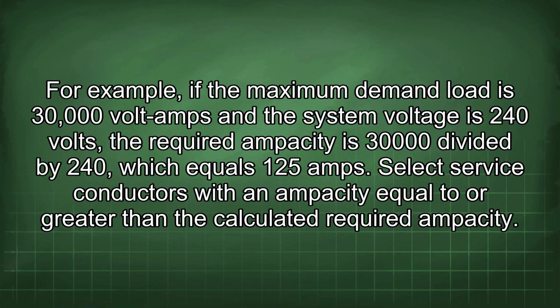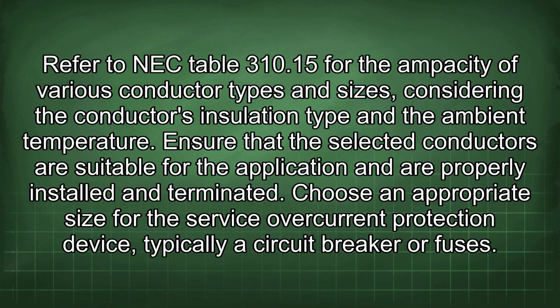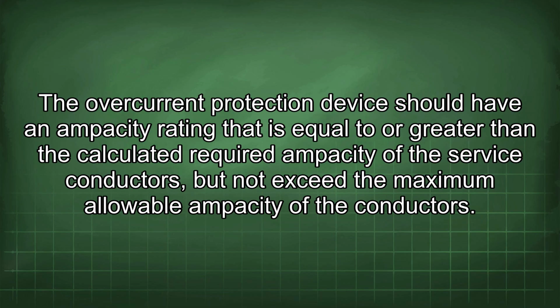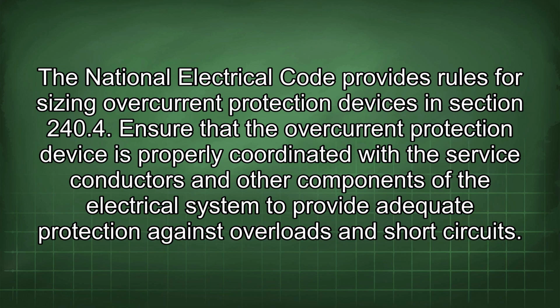Select service conductors with an ampacity equal to or greater than the calculated required ampacity. Refer to NEC Table 310.15 for the ampacity of various conductor types and sizes, considering the conductor's insulation type and the ambient temperature. Ensure that the selected conductors are suitable for the application and are properly installed and terminated. Choose an appropriate size for the service overcurrent protection device, typically a circuit breaker or fuses. The overcurrent protection device should have an ampacity rating that is equal to or greater than the calculated required ampacity of the service conductors, but not exceed the maximum allowable ampacity of the conductors. The National Electrical Code provides rules for sizing overcurrent protection devices in Section 240.4.